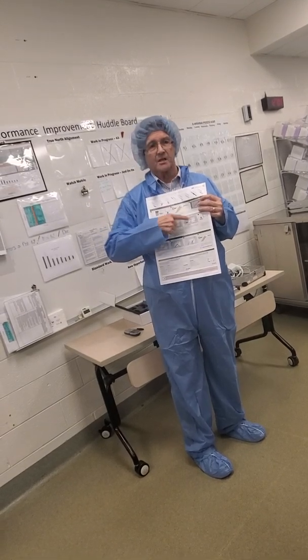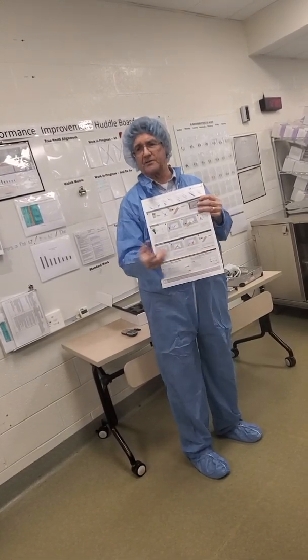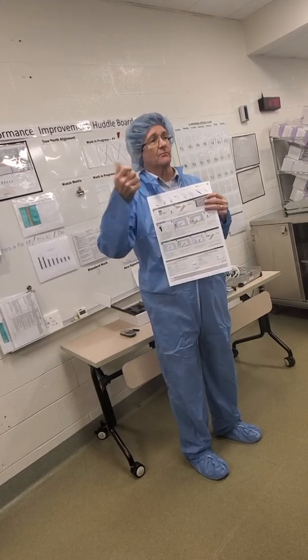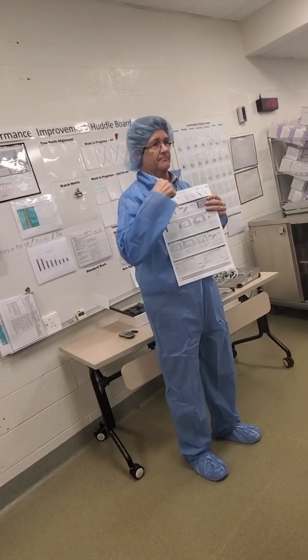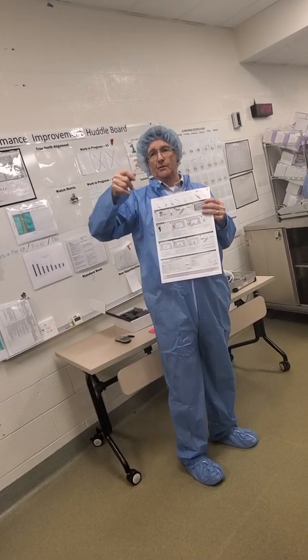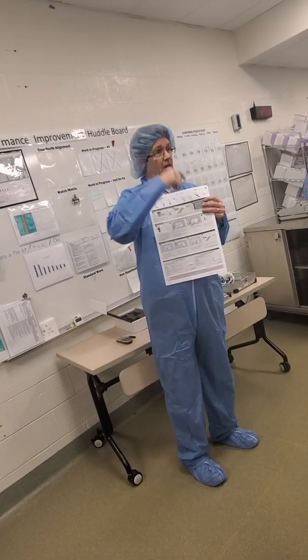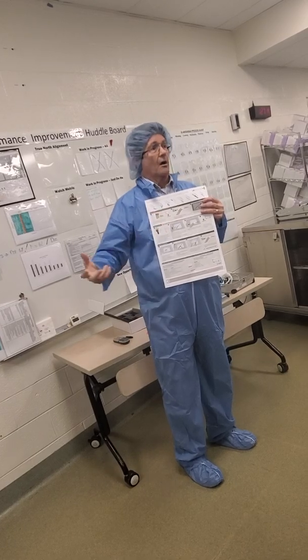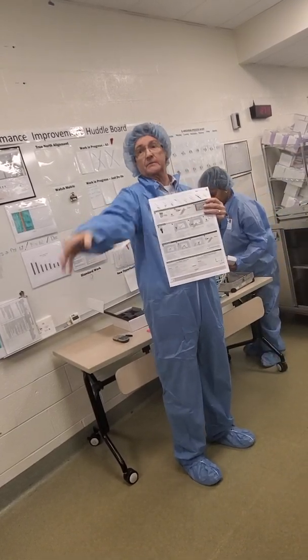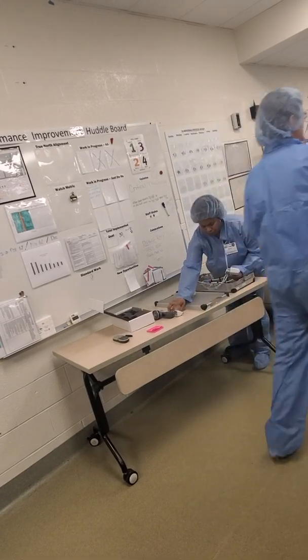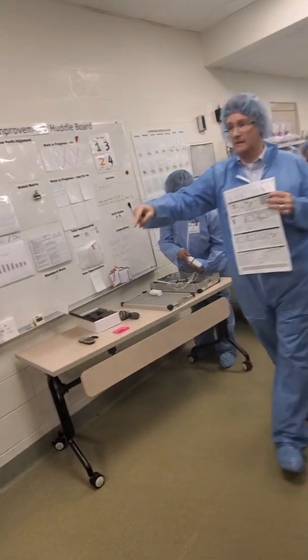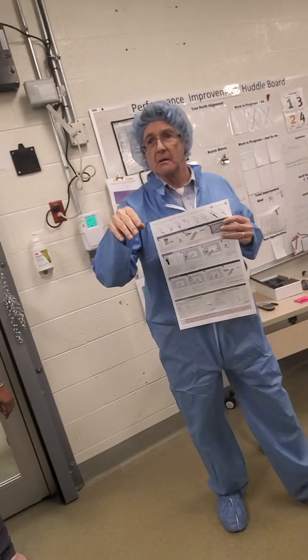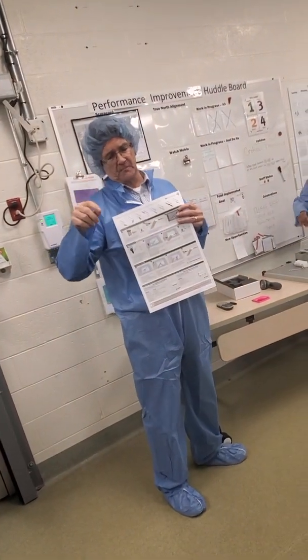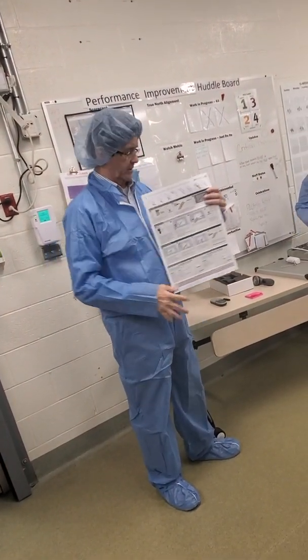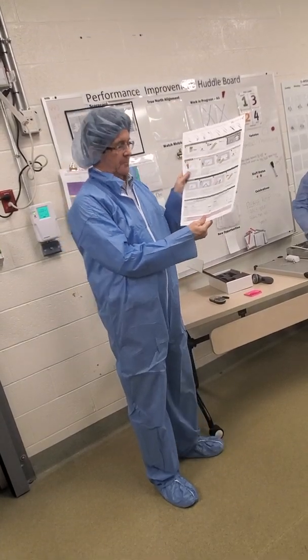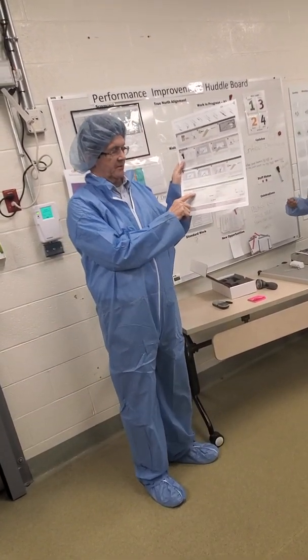Then you take it out, you dry it off just a little bit so it's not drippy. Then you can release the pressure on the bulb. I'll show you. Okay? Then you're going to take off the leak test cap and put the other cap back on. Put the cap on, clean it. Remember, you're going to leak test before you clean it. Before you clean it, it can't go in water with a leak. You know.